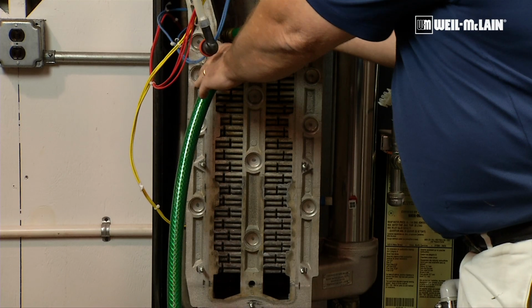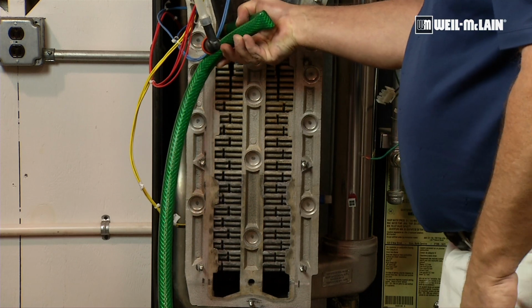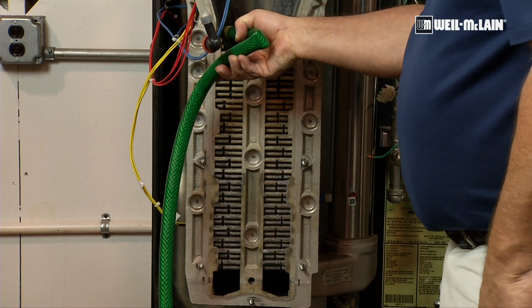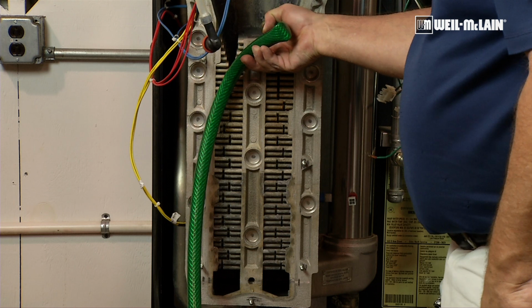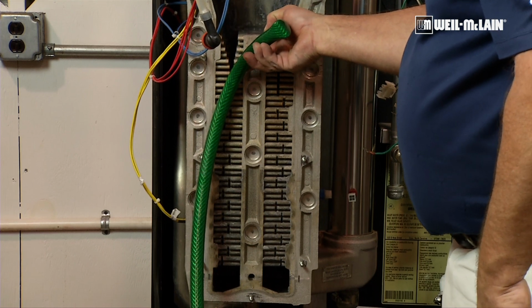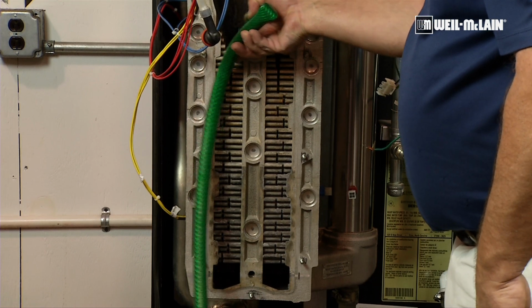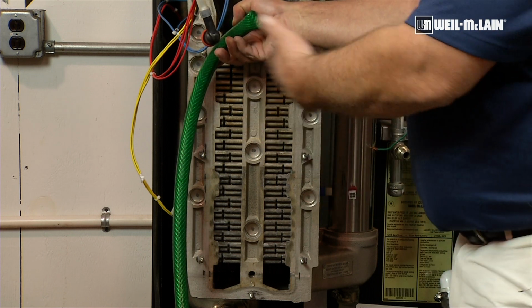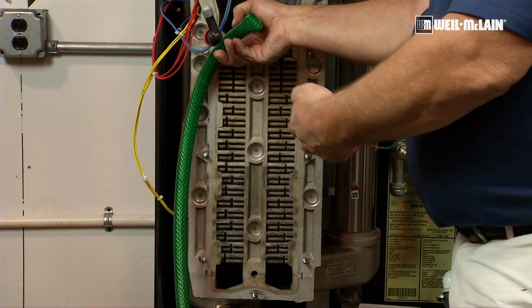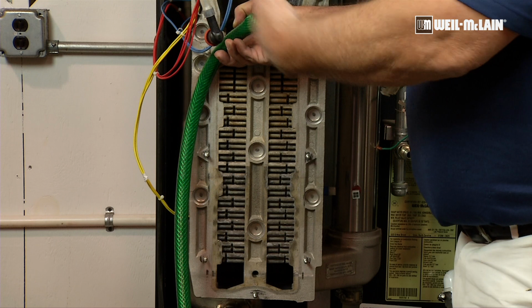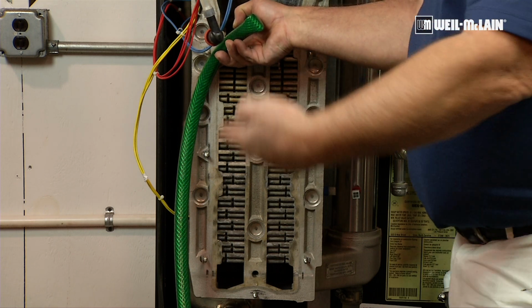Along with the rotating or the cleaning tool, it's recommended that you take a garden hose. And again, we're not talking about power washing here. If it's done properly, we don't get water all over everywhere. The water simply goes down the condensate trap. It goes into the condensate pump, or it goes to the drain.